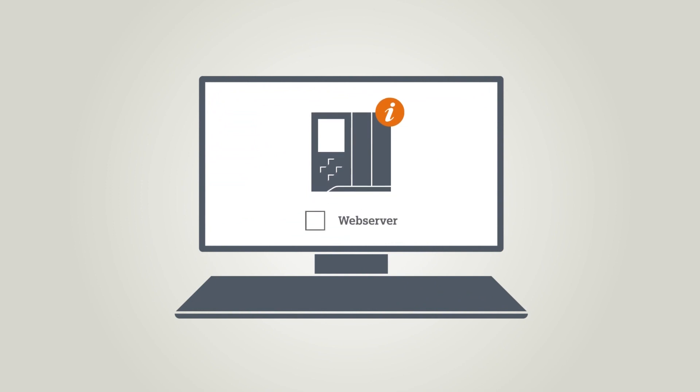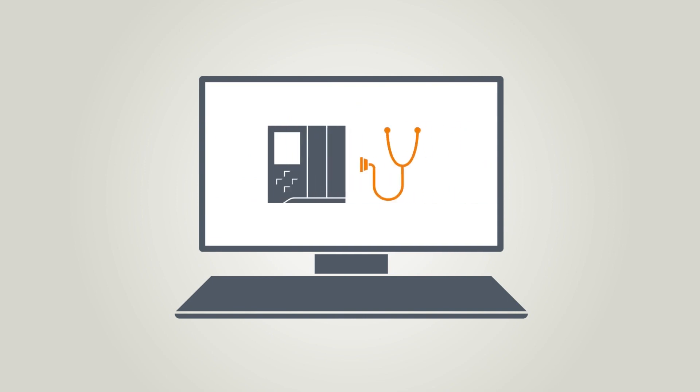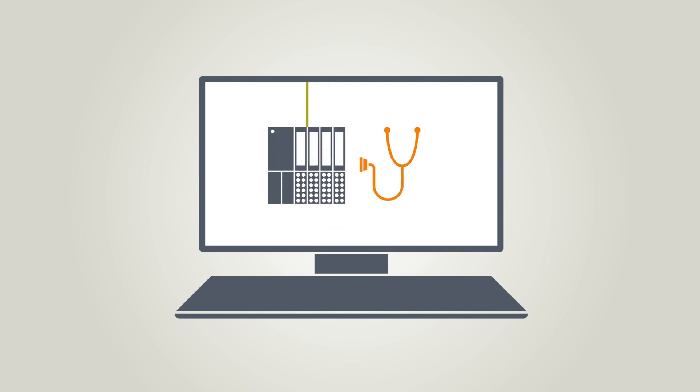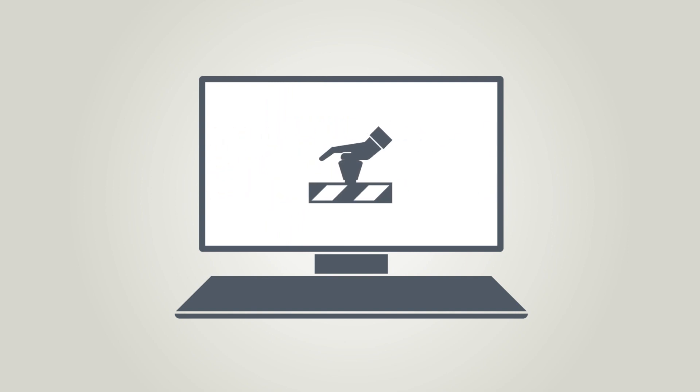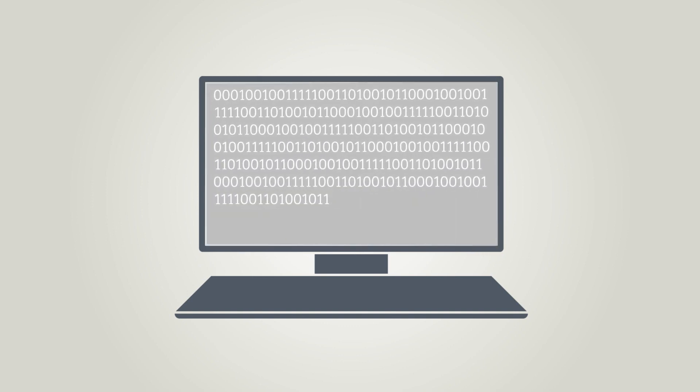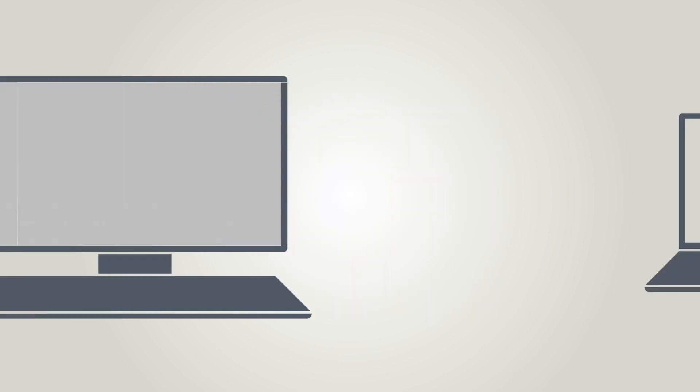All you need to do is activate the web server in the TIA Portal. Now you can see the firmware and the serial numbers, access the SD card, view the controller's LED status and use the controller's diagnostics function, including all components. This is also the case for all safety components and for faults right up to broken cables and short circuits. And there's no need to write even a single line of code.